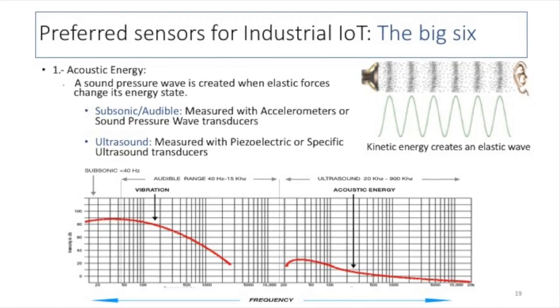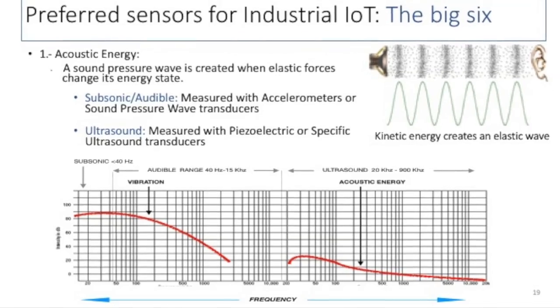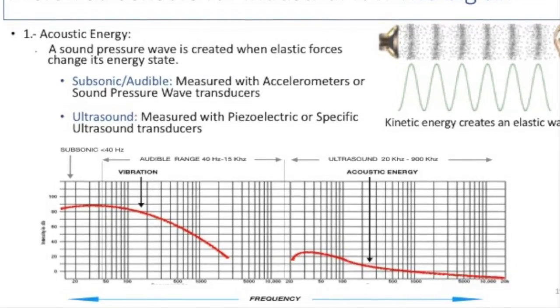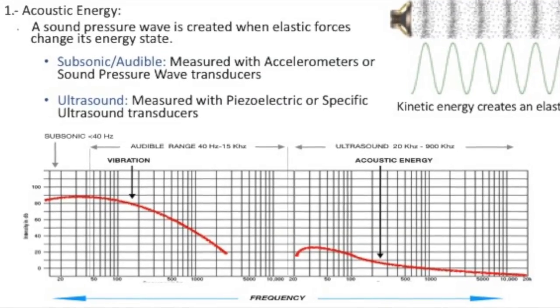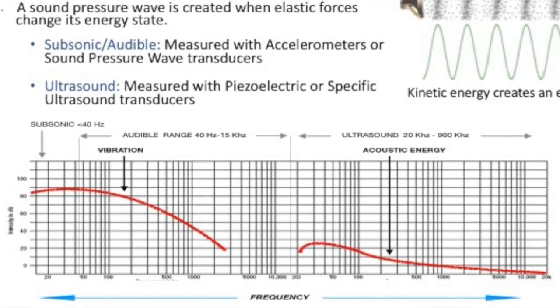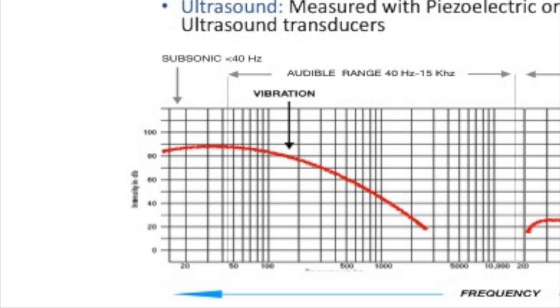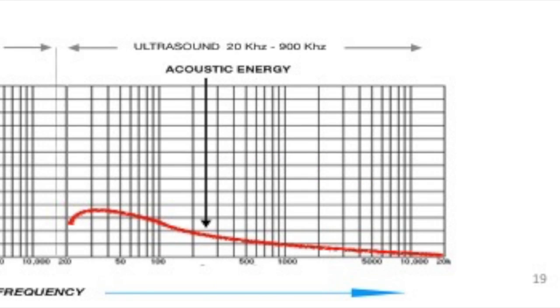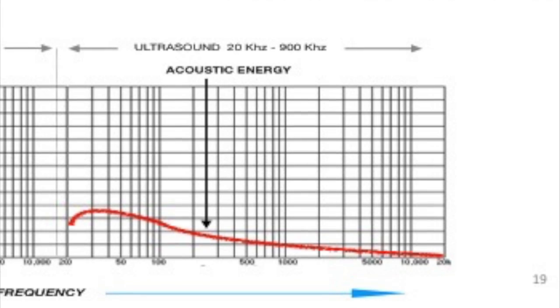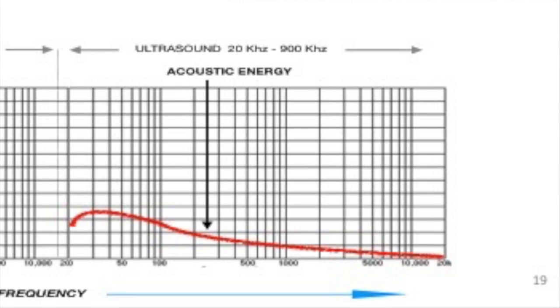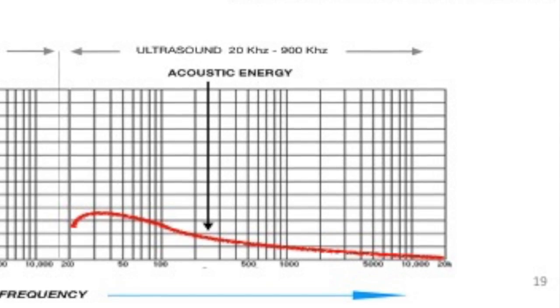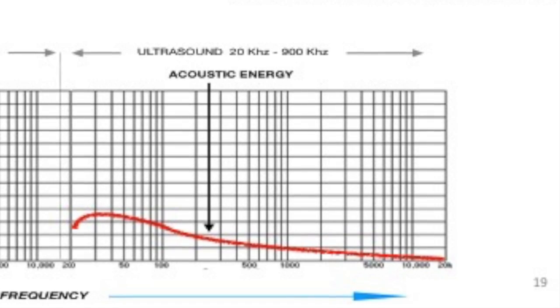So the first thing we use is acoustic energy by ultrasound analysis. Here I'm making a graph of vibration and ultrasound, so you will see the difference. For those of you who are not experts in digital signal processing or signal analysis, the spectrum is divided into subsonic and audible frequencies, which are usually measured with accelerometers or sound pressure wave transducers, and those frequencies are usually below 1 kilohertz, on the left side of the graph. Then on the right side of the graph you have the ultrasound frequencies, which are beyond the audible frequencies - we cannot hear ultrasound - and they're measured with piezoelectric or specific ultrasound transducers.